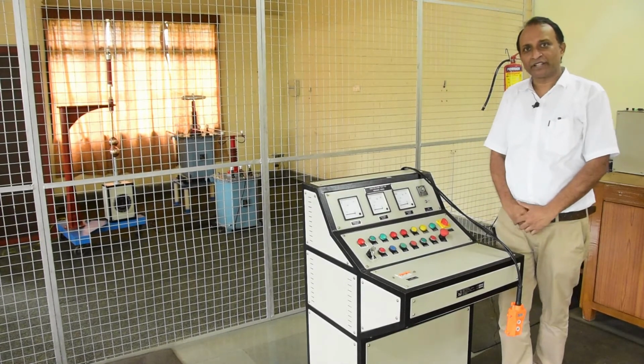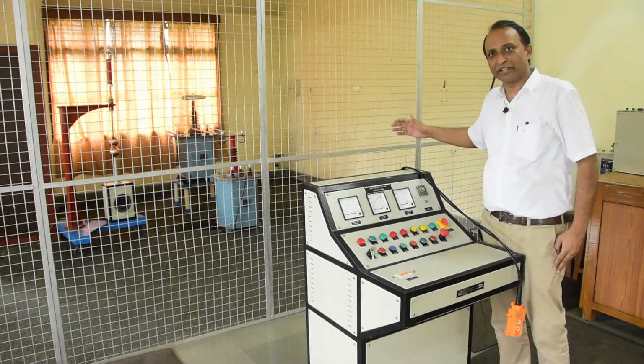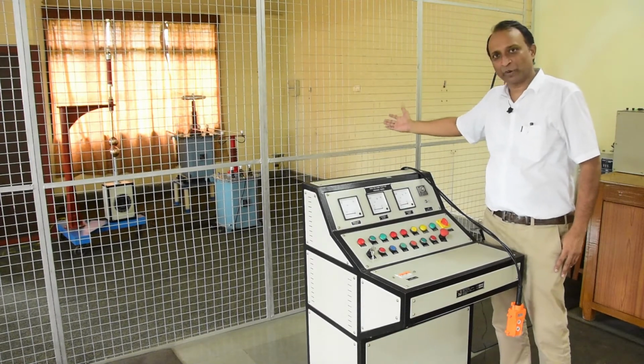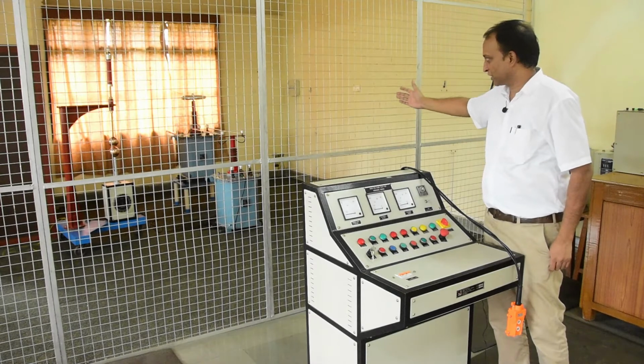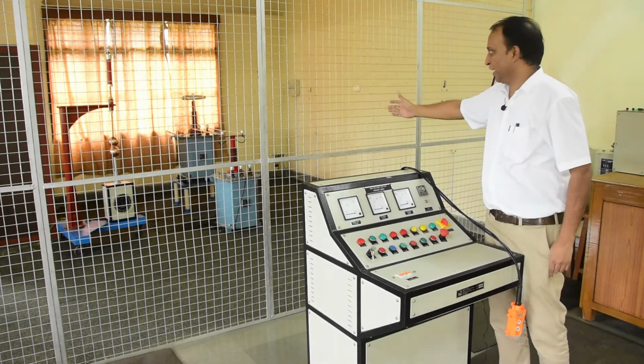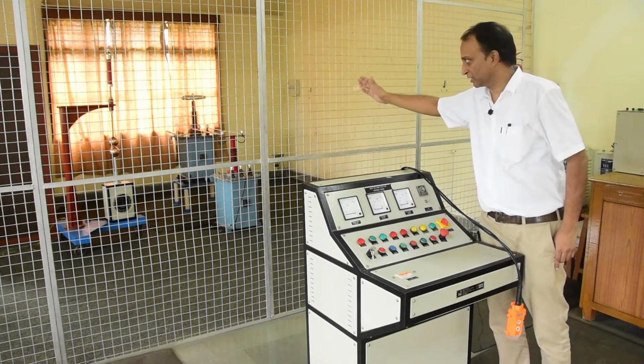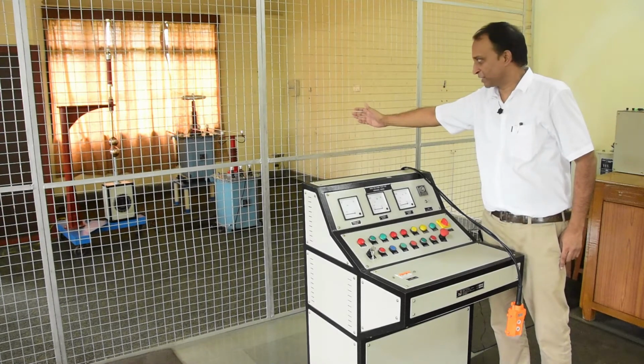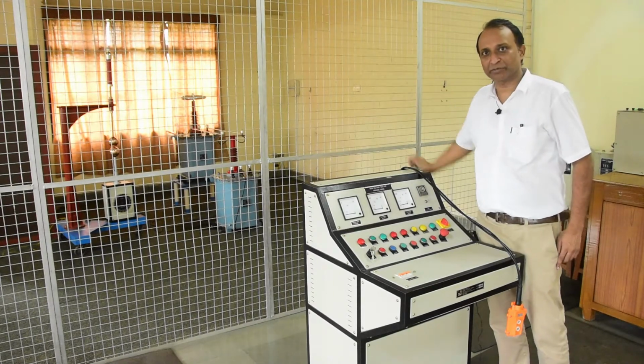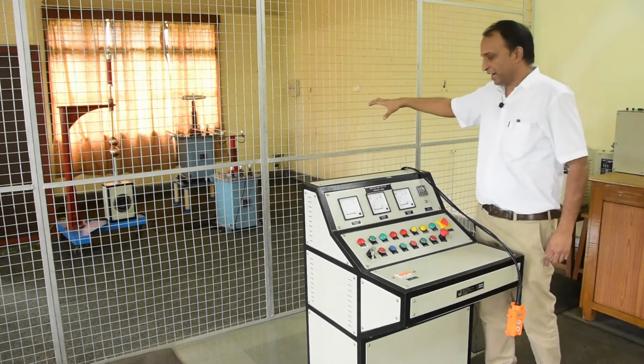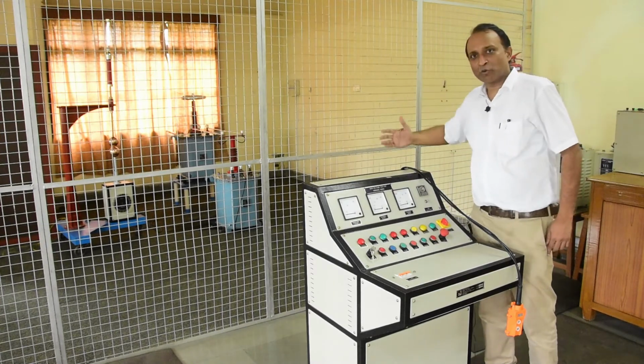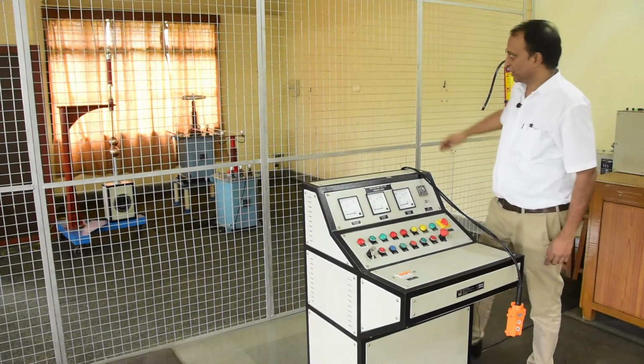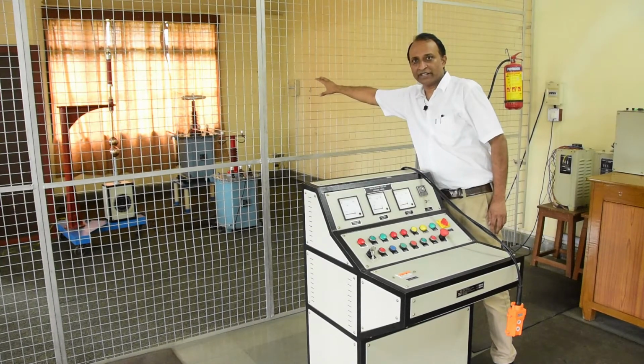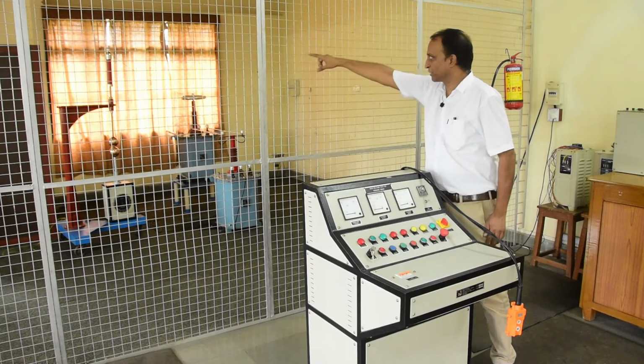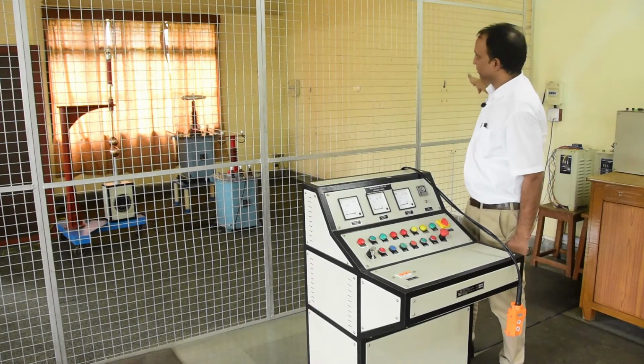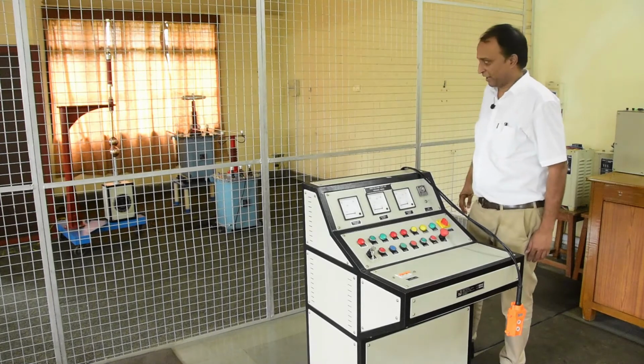We have already seen the assembly inside the cage, the high voltage cascade transformers, right? And also the sphere gap assembly and the settings for adjusting the spacing between the electrodes. So the dial and all that. Now we are standing outside the cage. Here you can see that this is a metal cage. This metal cage is surrounding this whole assembly on 2 sides, and the remaining 2 sides are walls, right?